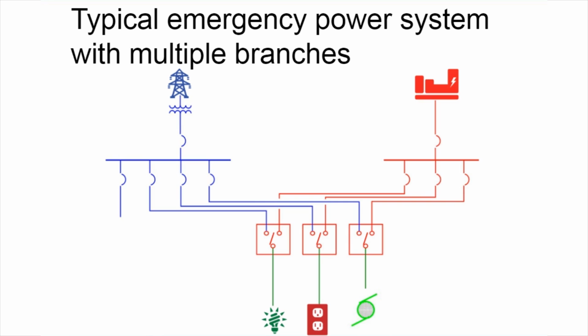If you look at a healthcare facility again, I can't tell you how many times I've gone to a hospital site and they tell me that they exceed code because 100% of their load is on the generators. So they picked everything up off their generators. Sounds good, right? Well, not so fast. The answer is it depends.